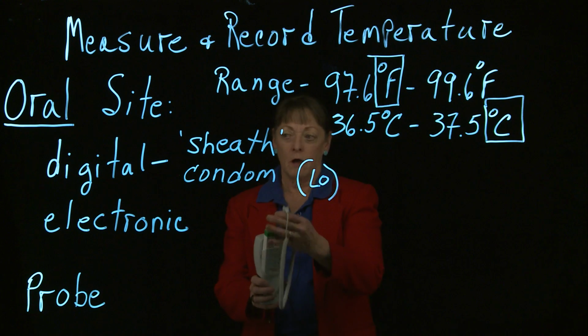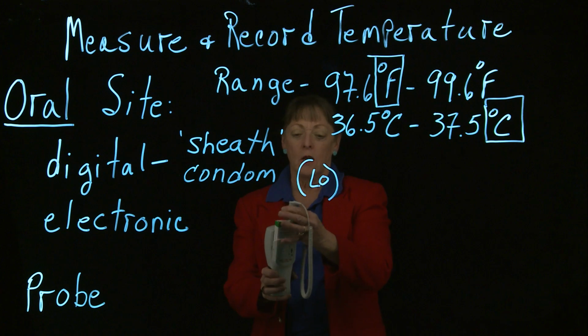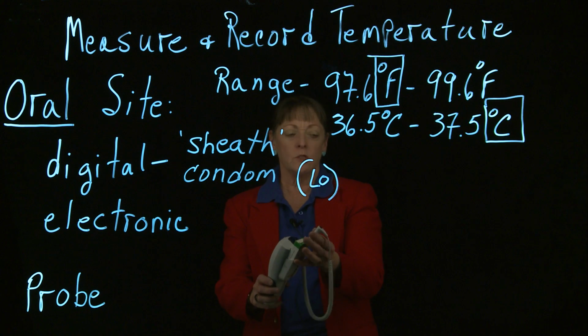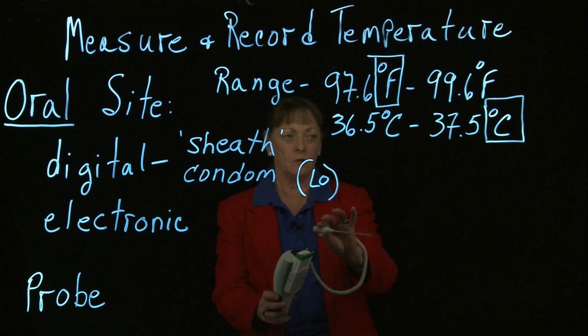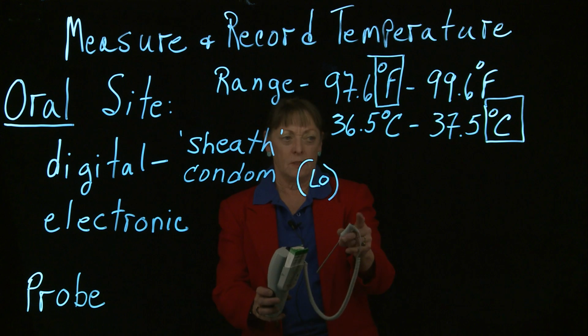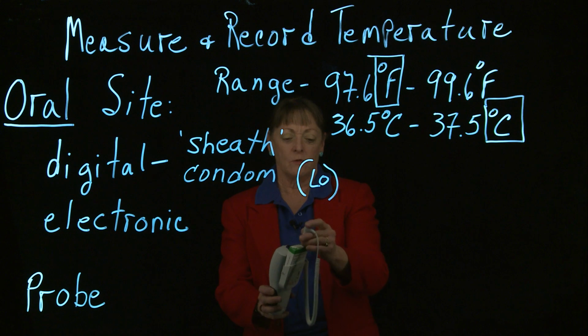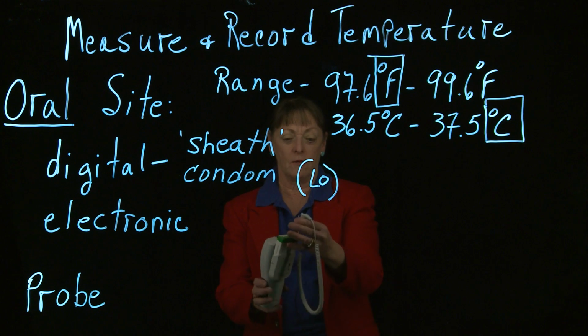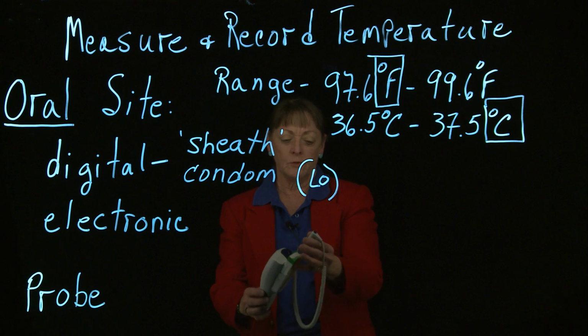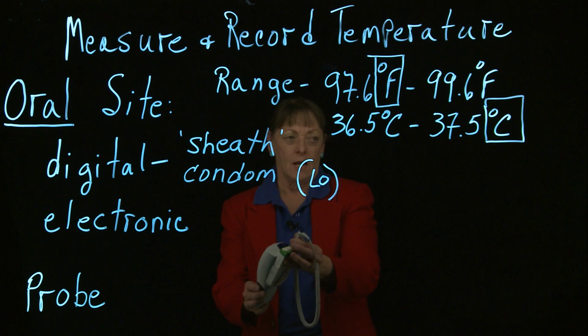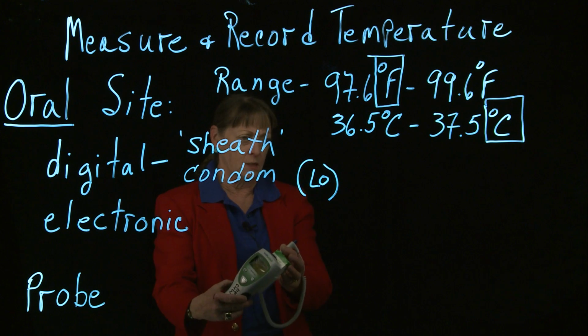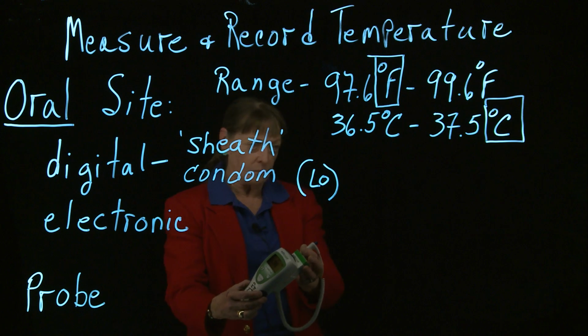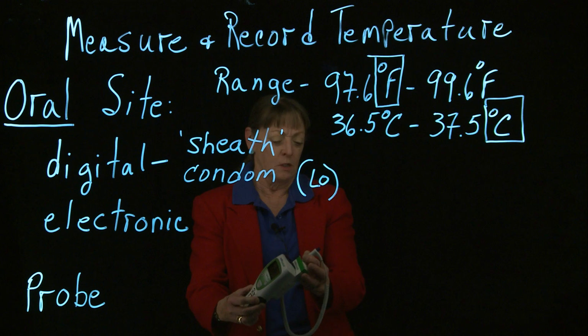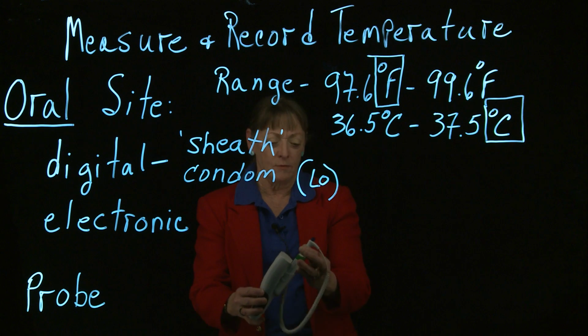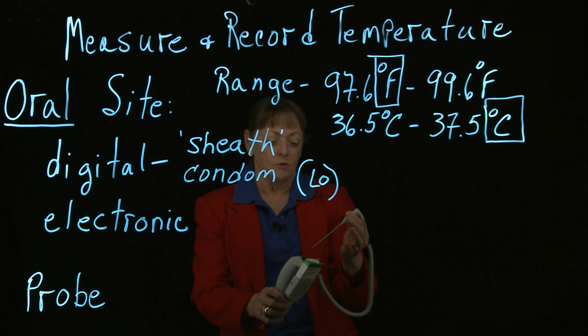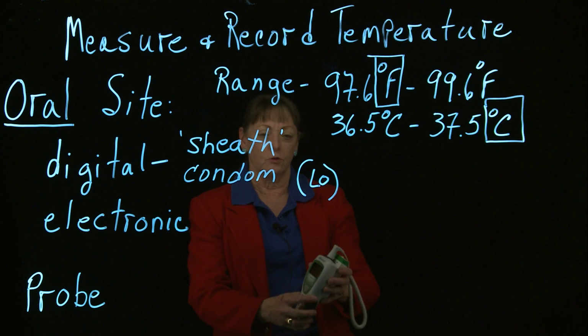So you put your probe inside the box, you pick up a cover. This is a little tricky to load. You need to hold it on the neck part of the probe, here on the neck, and not on the top piece, because this is the eject button. So if you're trying to load it and you can't, it's because you're telling it to eject at the same time. So you're going to put this in the box, push it into a probe cover, and then it's a little bit hard to see, but there's a button on top that will pop up that tells you that that probe cover is secured. And then you will place this in the person's mouth, and it will beep when it is finished. Now, there's a couple of things that you need to look at before you use these instruments.